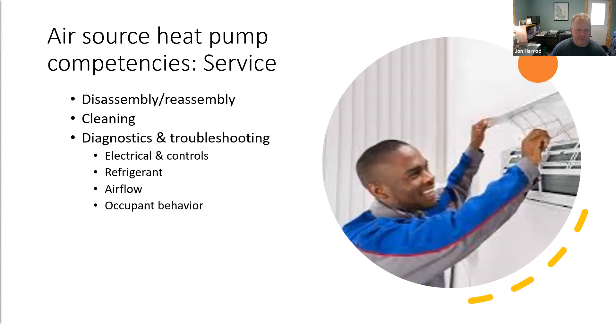A lot of the tools on the service side involve just being comfortable assembling and reassembling these items and giving them a real thorough cleaning. But there are some pretty sophisticated diagnostics and troubleshooting skills. You need to be able to work your way through a troubleshooting diagram to test voltages at different points, to handle refrigerant comfortably, to measure airflow. And you also need to be able to talk to occupants about the things they're doing that might be preventing them from getting the results they're looking for.